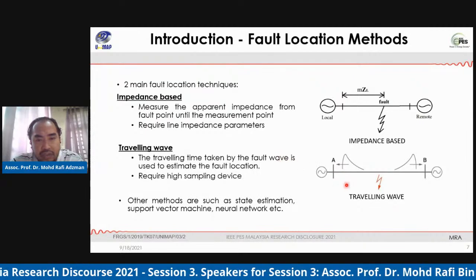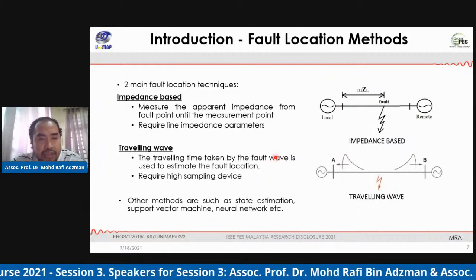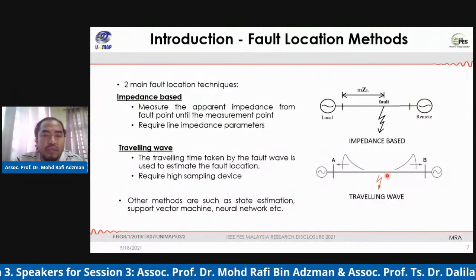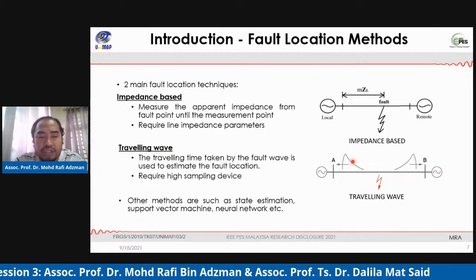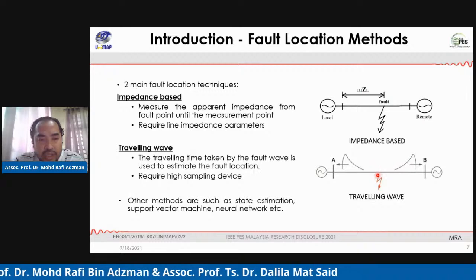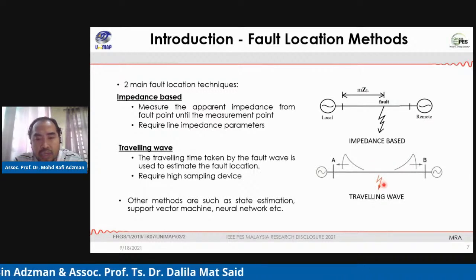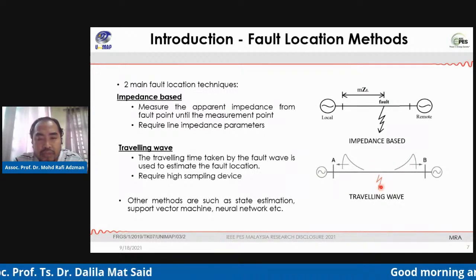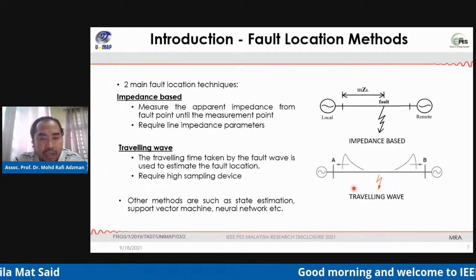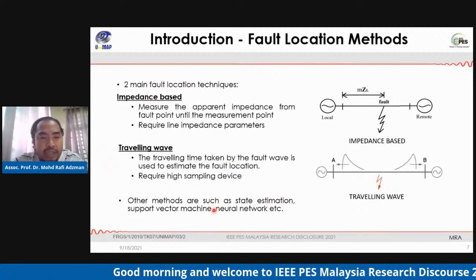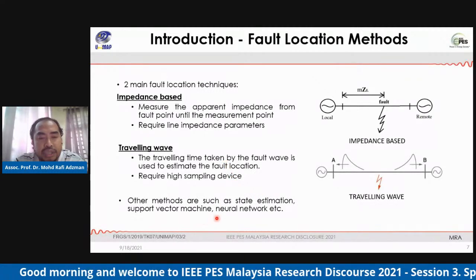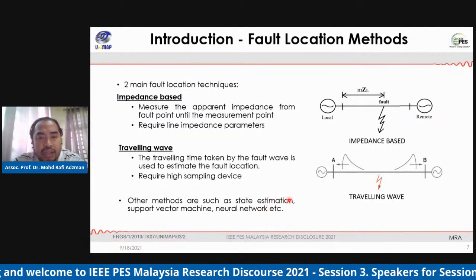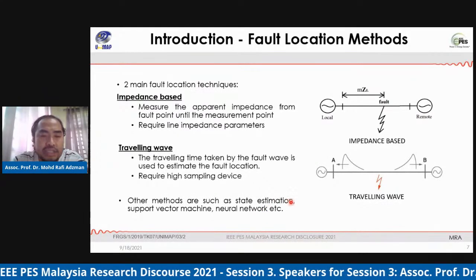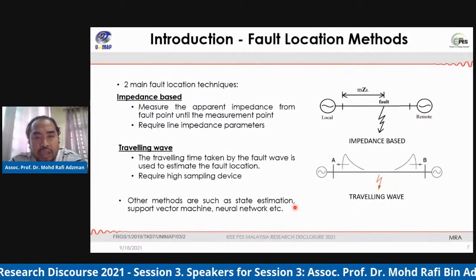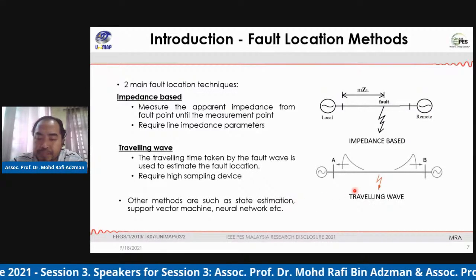The second method is known as traveling wave, or TW. The traveling time taken by the fault wave is used to estimate the fault location. This method requires a high sampling device in order to read the fast traveling wave. Other than these two methods, we can use state estimation, support vector machine, neural network, and other artificial intelligence techniques to locate the faults in the line.